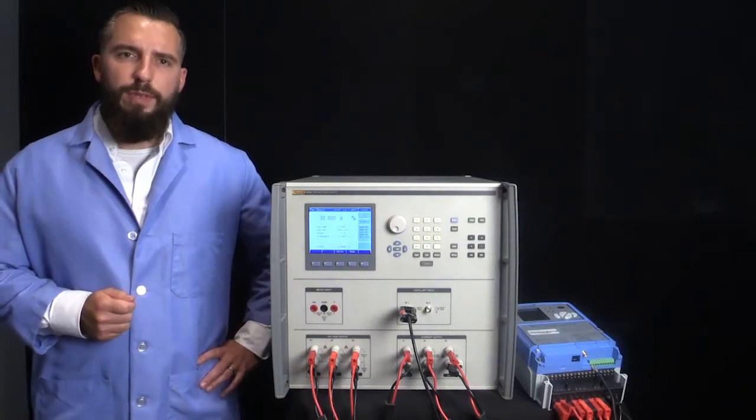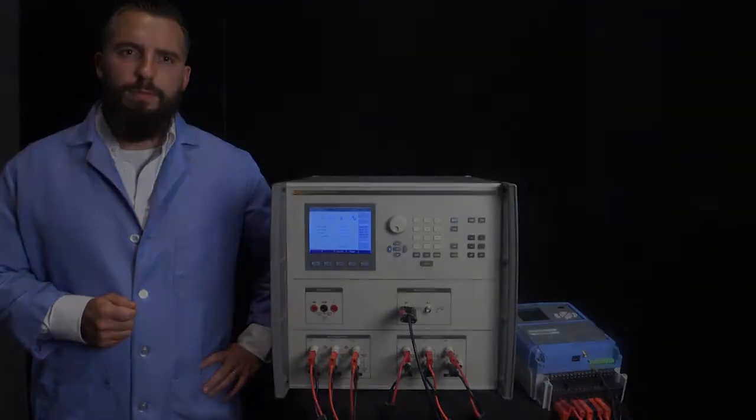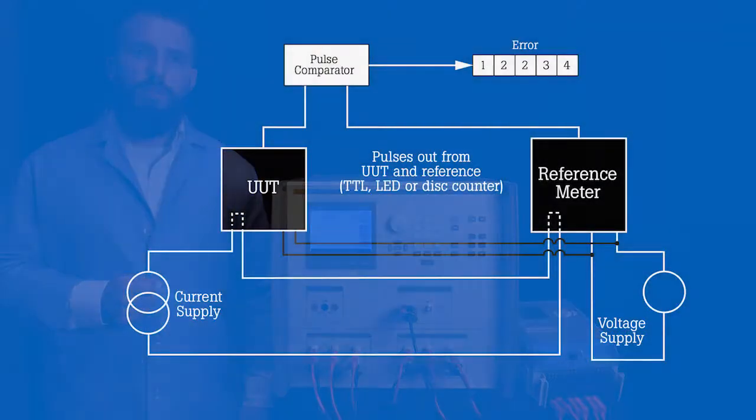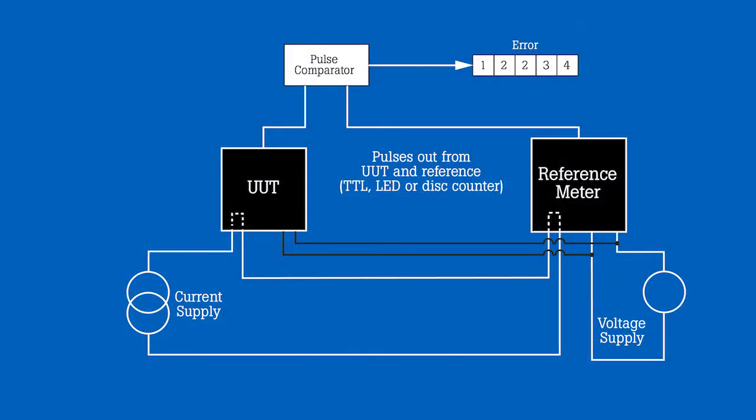Each pulse represents a specific number of watt hours. Calibrations are traditionally performed using a reference measurement technique where a known amount of energy is simultaneously supplied to a reference meter and the meter under test. A reading from the reference meter is then compared to a reading from the UUT and the error is calculated.